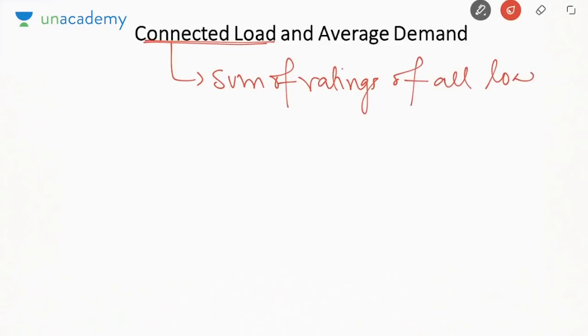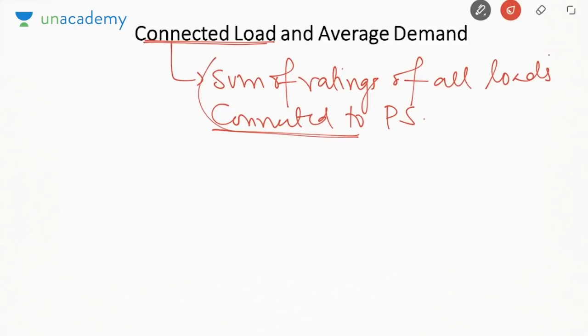Next term comes connected load. Now, suppose in our homes we have 4 tube lights, 5 fans and then 2 ACs. But not all will be working at the same time, but all will be counted as the connected load. So connected load is nothing but the sum of rating of all loads that are connected to power system, whether or not they are on or off. So connected load will be taking all the loads into consideration, even if it is working or even if it is not working. That means whatever load is connected to power system is called as connected load. So we will see how it is important.